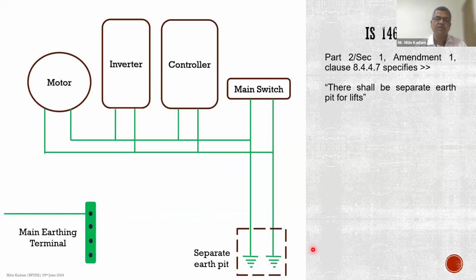One of the misconceptions about the earthing on the site is, there was an amendment that had happened on IS 14665, and since IS 14665 is still running, it is concurrently running along with 17900. The Part 2, Section 1, Amendment 1 of clause 8.4.4.7 specifies that there shall be a separate earth pit for lifts. Now, this is somehow a sort of a mistake that has happened in the elevator codes in the past. And if you see on the side, a separate earth pit is given, and from this earth pit there are two separate earth conductors which are going to the main switch, the controller, the inverter, and the motor.